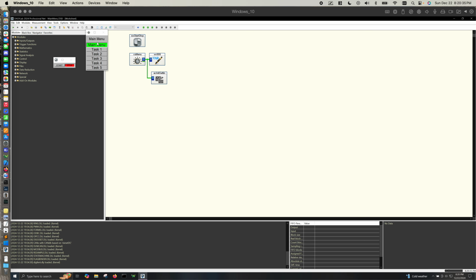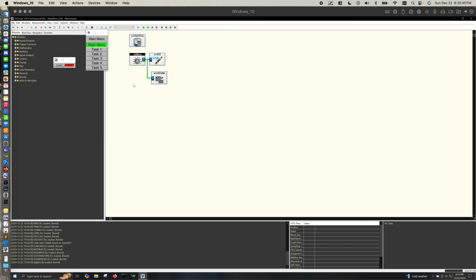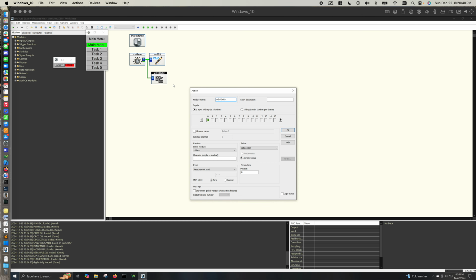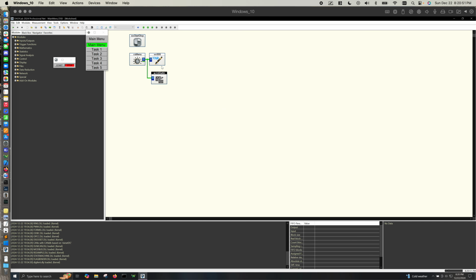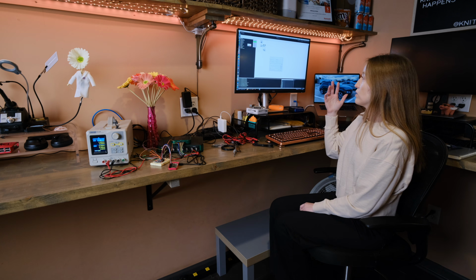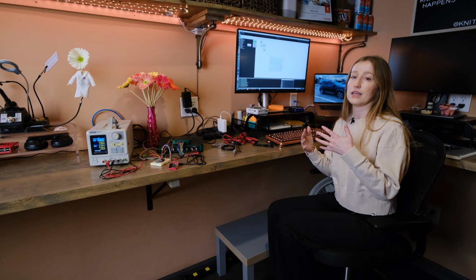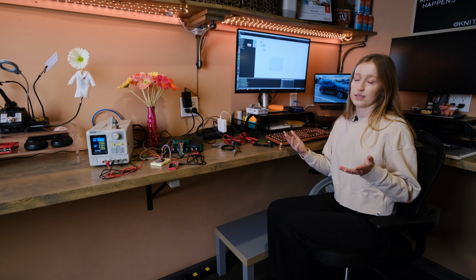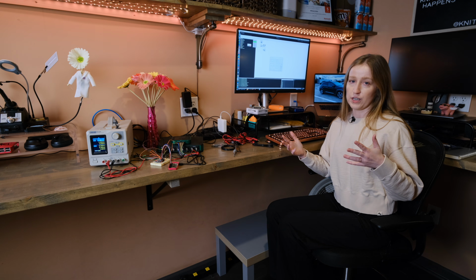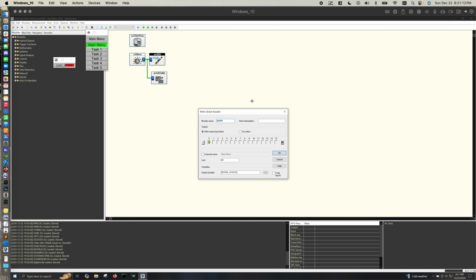There's a menu task in here, so in your menu you have all the different tasks you can choose, and then an actual start-stop button, which leads into an action module. Because this is part of an overall sequence, you'll use global variables to talk between different worksheets in a sequence, just like any other software application, where different functions call from different source files.